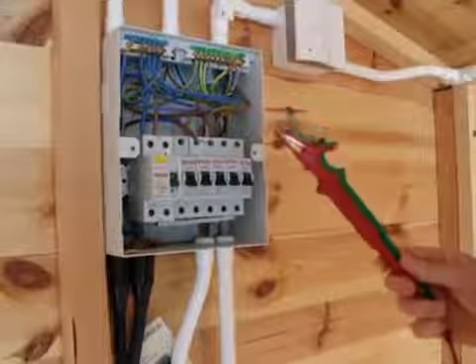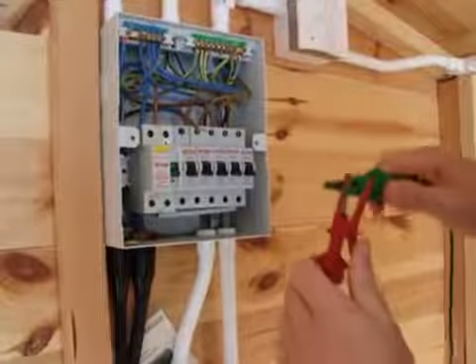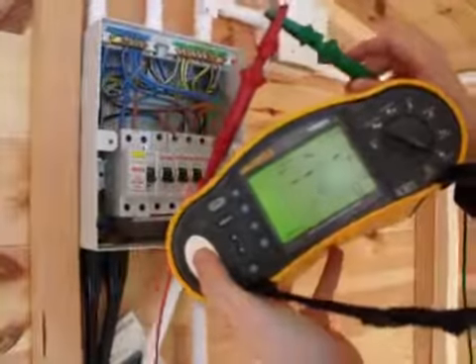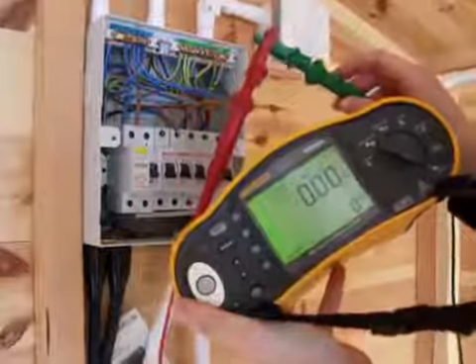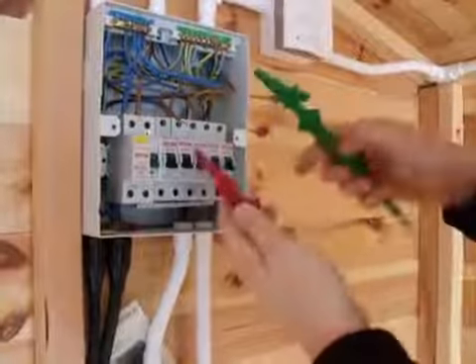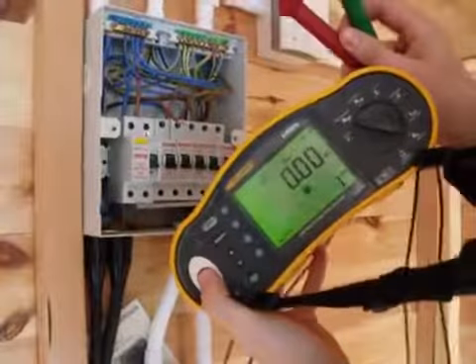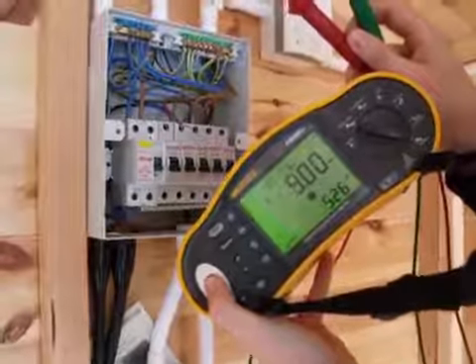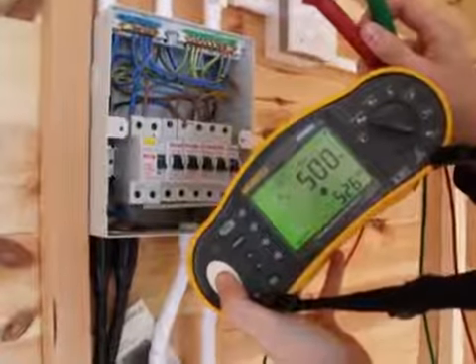As with most tests, we want to make sure our tester is working. We put our crocodile clips together, press test, and we can see it's come up at 0.00 mega ohms — that's basically a dead short. Then we open up our test leads and do the same test. This should come up over 500 mega ohms. You can see in the bottom right-hand corner the current test voltage is 526 volts DC.